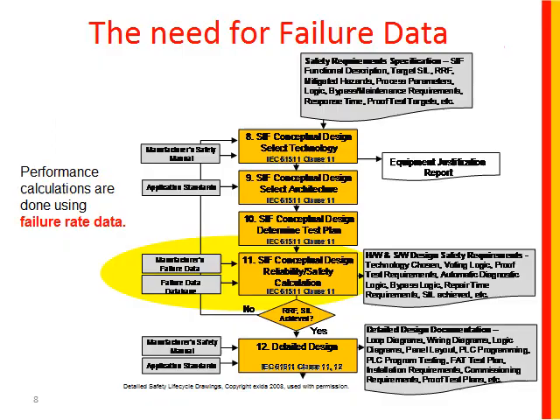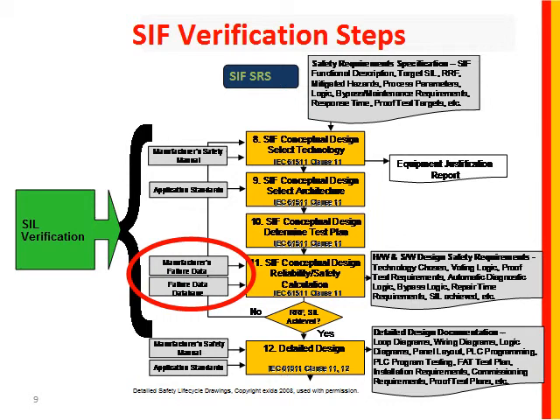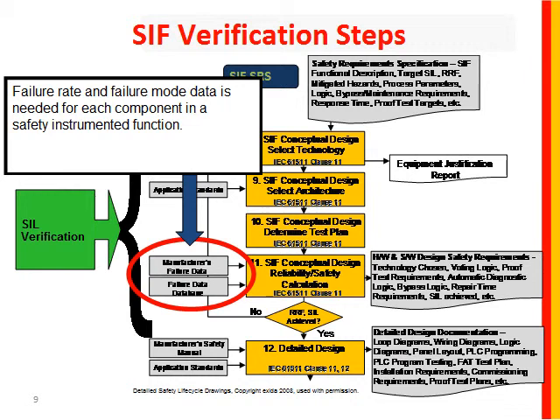Let's talk about failure rate data. Many of you signed up for the seminar because you understand the need for failure data. In the safety lifecycle, for IEC 61508, 61511, and other derivative performance-based standards, failure data is used to verify a given design. We need failure data, or if we don't have specific data, we can get it from an industry database. The bottom line is we need failure rate and failure mode data for every component in a safety instrumented function.